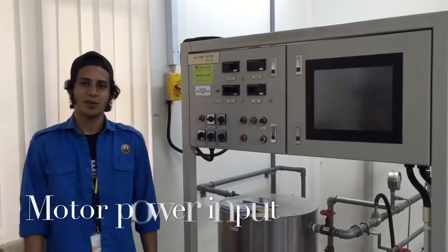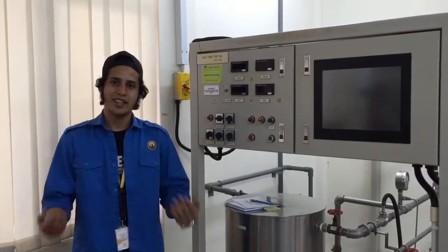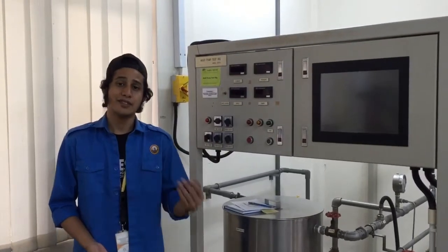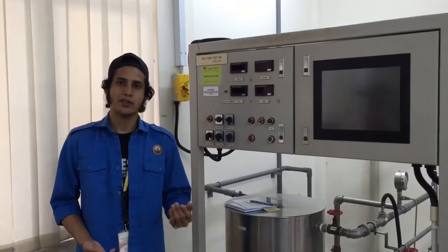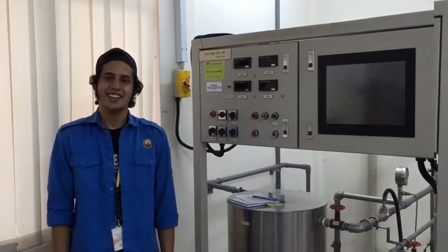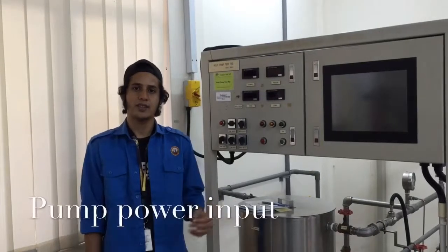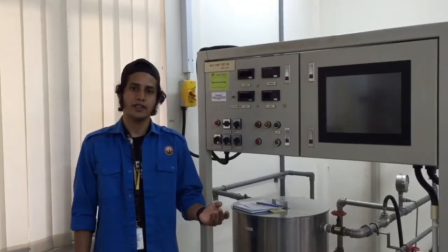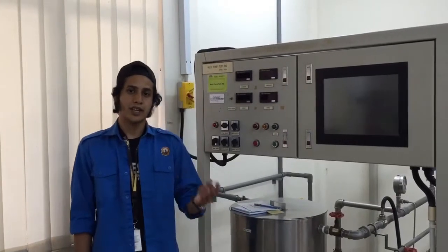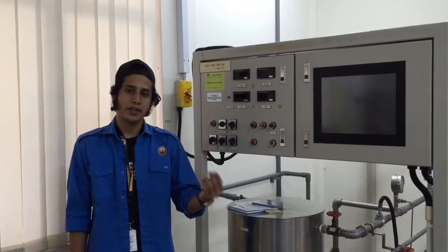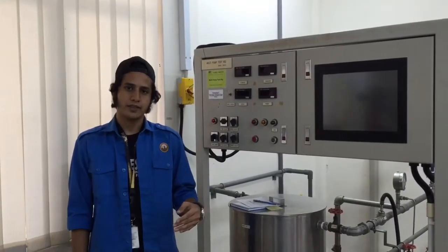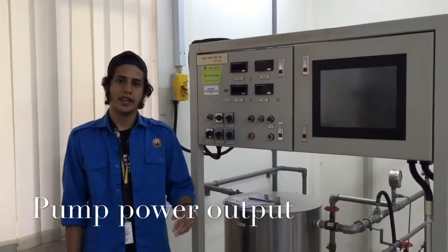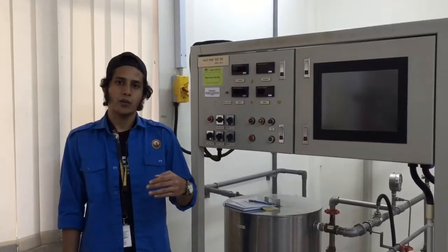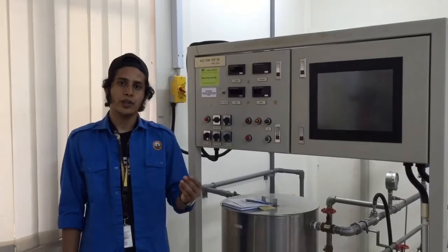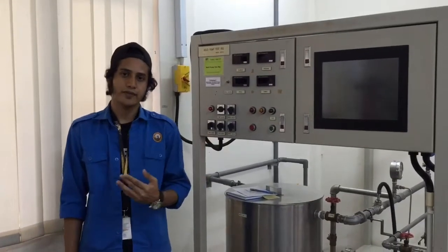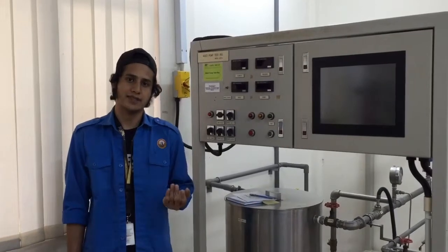The next one is motor power input, which indicates the energy that is converted from electrical to mechanical and then supplied to the pump for the work. Pump power input indicates the amount of energy converted from electrical to mechanical, which is supplied to the pump in order to turn the shaft. Pump power output is the energy converted from the work produced by the shaft to the fluid flowing through it, which is known as the hydraulic energy.